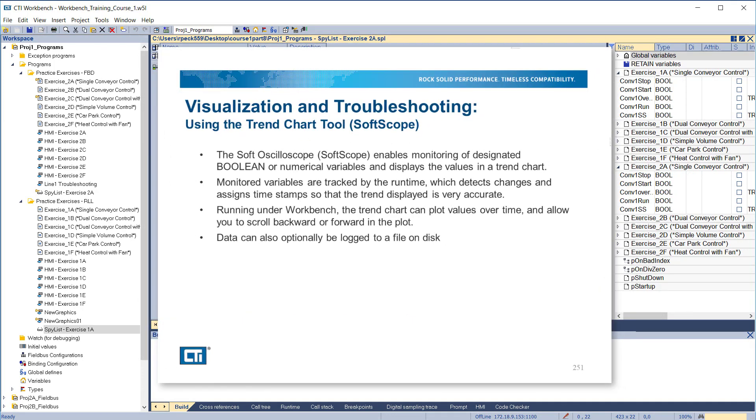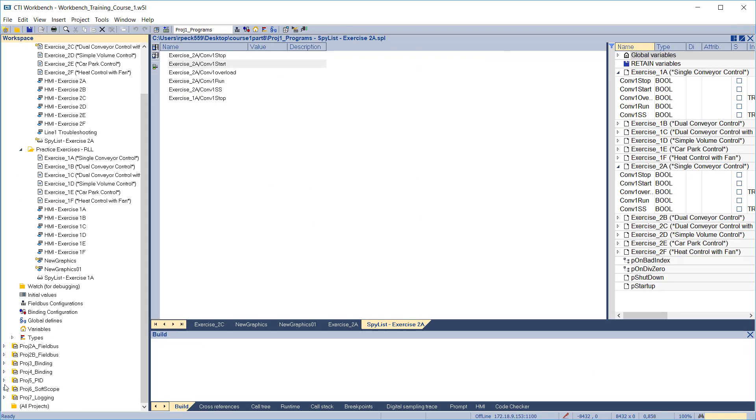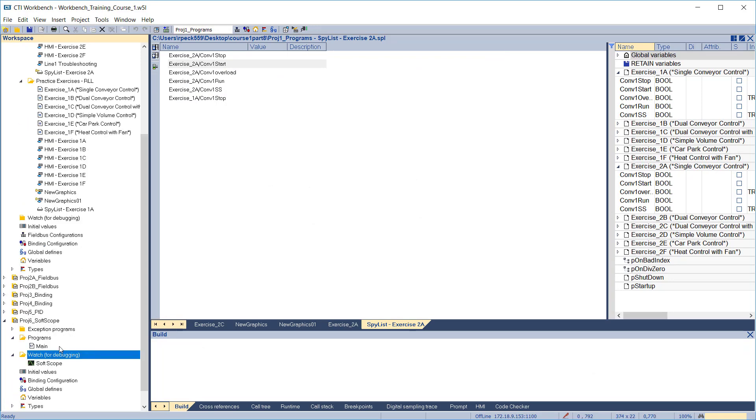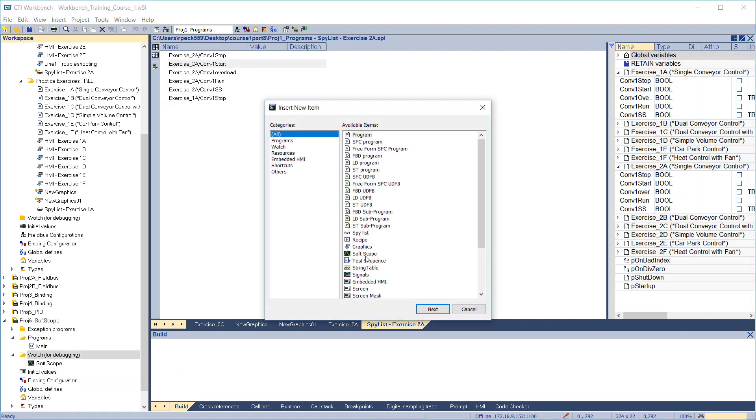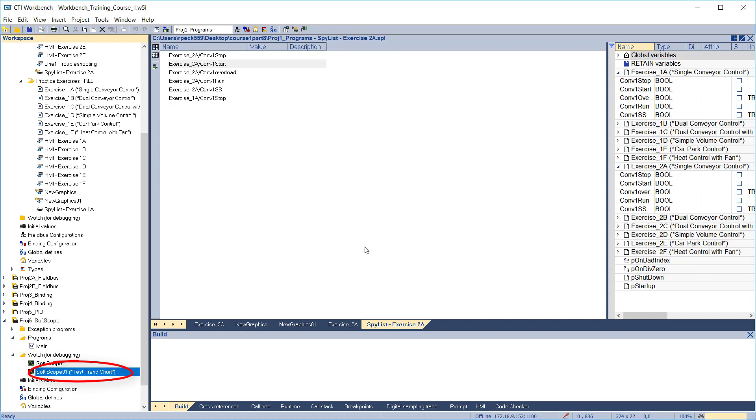Another very useful visualization and troubleshooting tool is the Trend Chart, or Soft Oscilloscope, Soft Scope for short. The Soft Scope enables monitoring of designated Boolean or numerical variables and displays the values in a trend chart. Monitored variables are tracked by the runtime, which detects changes and assigns timestamps so that the trend displayed is very accurate. Running under Workbench, the trend chart can plot values over time and allows you to scroll backward or forward in the plot. Data can also optionally be logged to a file on disk. To create a Soft Scope, right-click on the folder where you want to create it, click Insert New Item, then select Soft Scope from the list. Enter a new name and description for this Soft Scope. We'll call it Soft Scope 1.